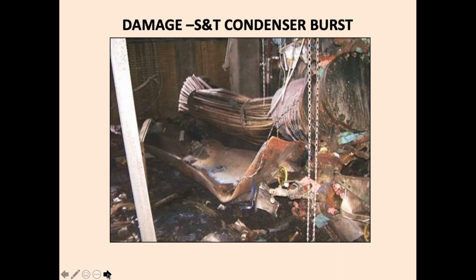See this accident: the discharge pressure cutout, which I mentioned, in a plant was bypassed. The water flow to the condenser was choked because of the filter. There was no water flowing through the shell and tube condenser, and the pressures rose beyond design pressure limits, and the entire plant burst. This happened in Pune. I will not name the customer, but the accident was so severe that not only the refrigeration equipment collapsed, but even the entire building collapsed because of such a high pressure wave developed inside the machine room.